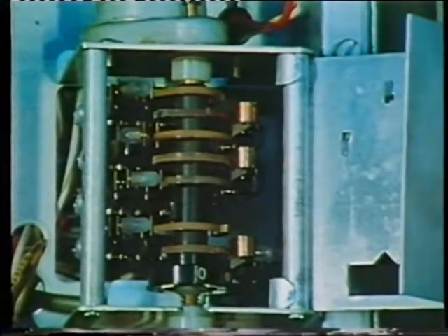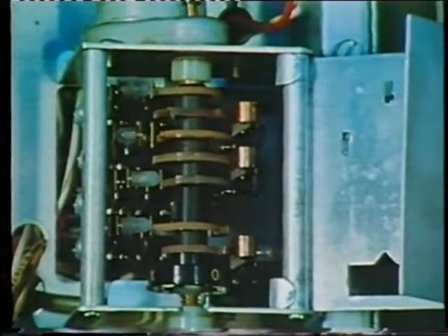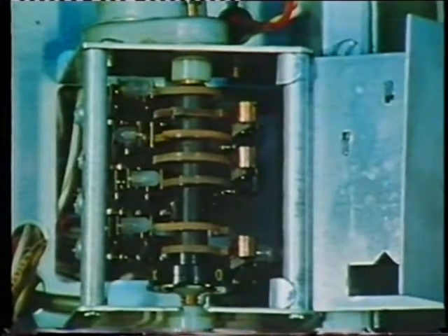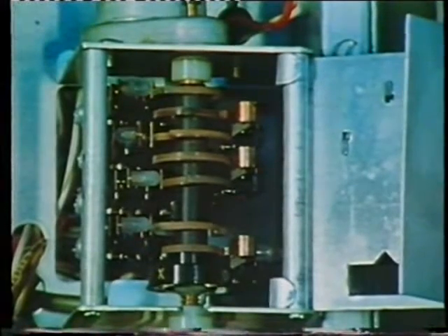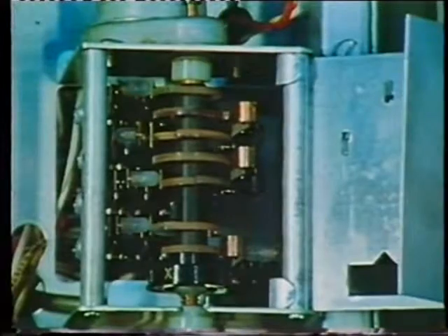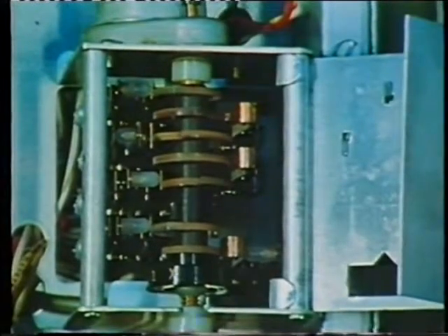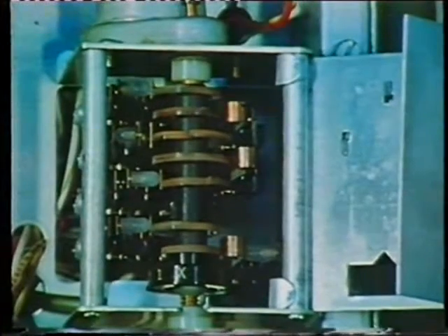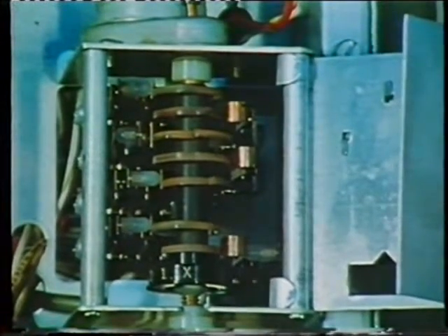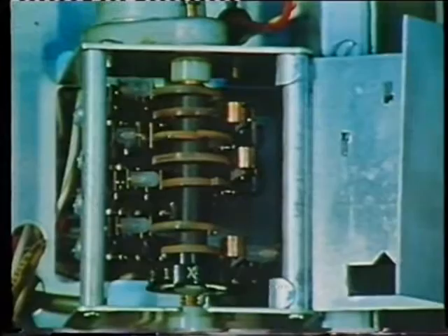When the burner is turned off by an operating pressure control or flame failure, the timer will run through a post-purge sequence and stop at the ready position to start another firing cycle. While the program timer is stopped at the main flame or run position, and with the controller set at automatic operation, the modulating pressure control will control the flame according to load demands on the boiler by means of the modulating motor, cams, and dampers.